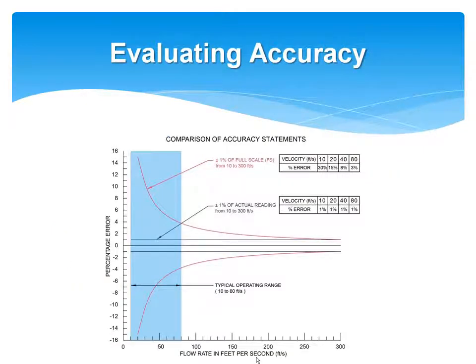This is a graph that compares a couple of very similar accuracy statements. The red set of lines is a 1% of full-scale accuracy statement, and the set of blue lines is a 1% of rate, or reading, accuracy statement. You can see, out towards the right side there at high flow rates, that they're very similar in terms of performance. But as you get into more of the typical operating ranges of most systems, you can see there's a very big difference in performance of the meter. And this type of statement actually applies to temperature measurement and pressure measurement. So again, it's very important to make sure that everyone understands the different types of accuracy there. And again, standardization will help that tremendously.